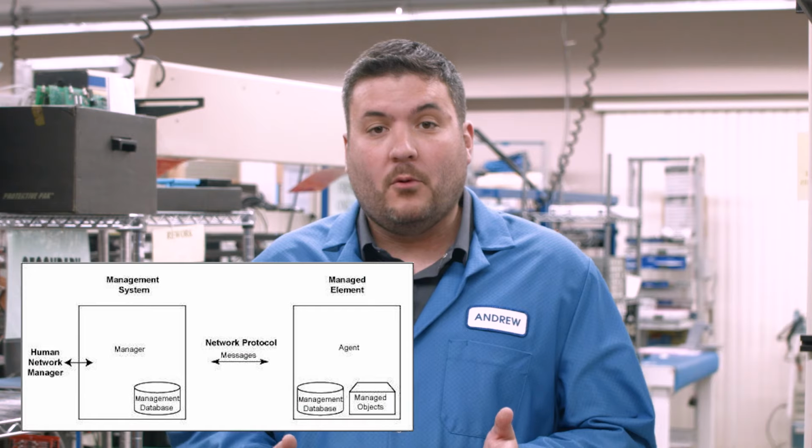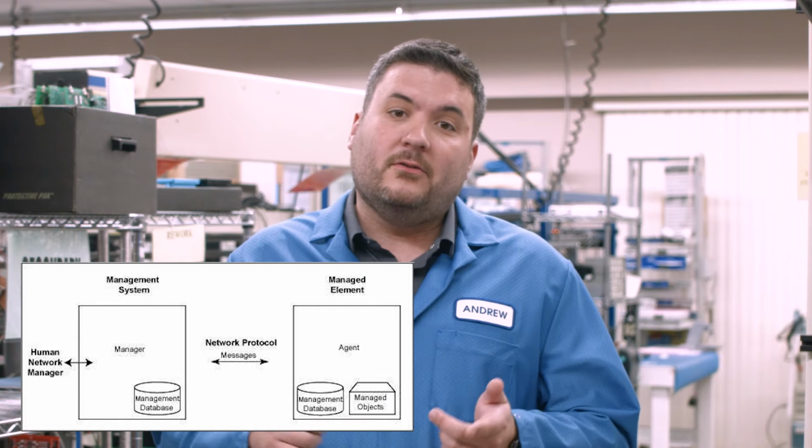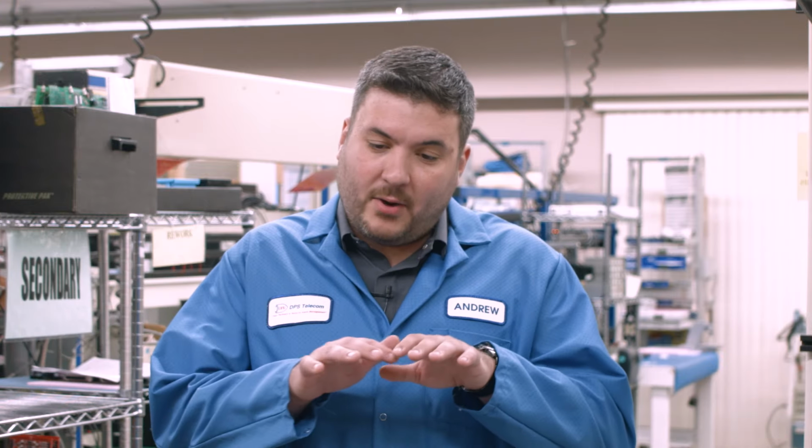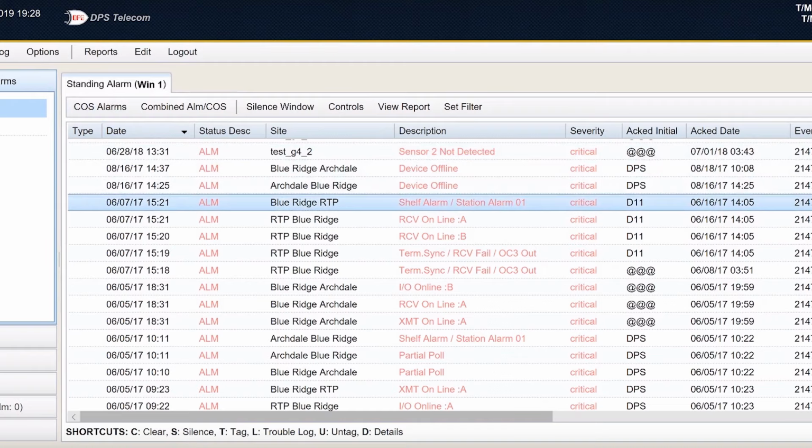Let's start off first with a quick definition. A protocol is really nothing more than a language that 2 computing devices use to talk to each other. And in a remote site management context, that usually means that you have boxes out at each remote site called RTUs, and those are going to collect various data from sensors and being connected to other equipment. And they need to send a message up to a central master station that's going to collect all that data and put it in some kind of an intelligible report or screen for you or send alerts to people. So the protocol we're talking about here is RTUs talking to a master station with a protocol in between them.